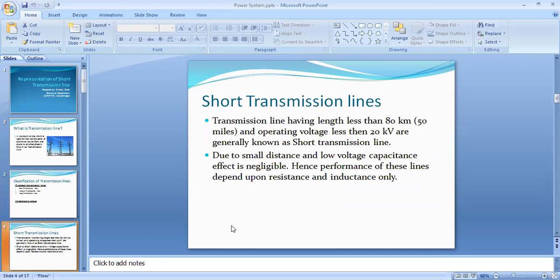Depending on the length and voltage, we can classify these three transmission lines. Short transmission lines have a length less than 80 km and an operating voltage less than 20 kV. Due to small distance and low voltage, the capacitance effect is negligible — only resistance and inductive effect are considered.